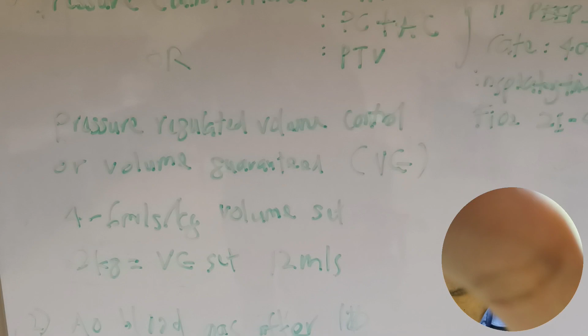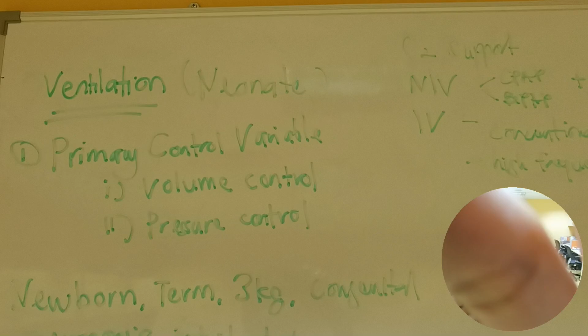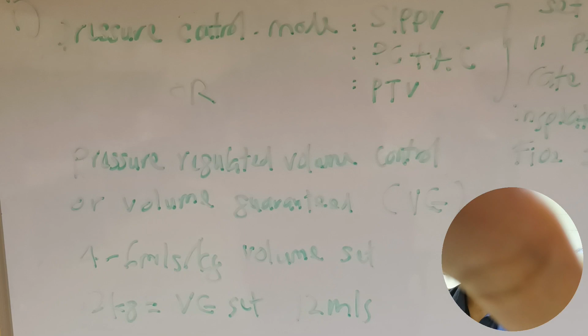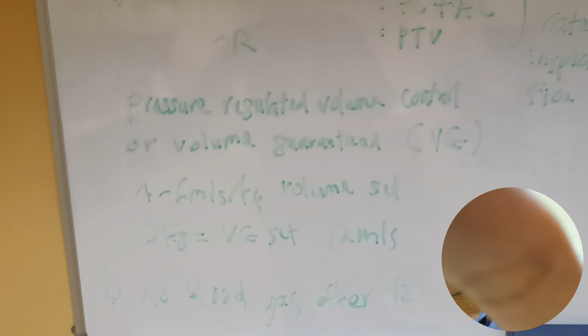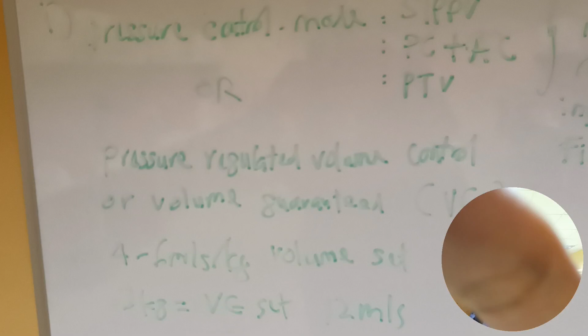So if it's purely volume control, the machine will just give however much pressure it needs just to achieve that. Basically there is no limit to how much the machine can give. But in pressure regulated volume control or volume guaranteed, it depends on the airway resistance and the patient's status at that time, so the machine can put a limit on that pressure.